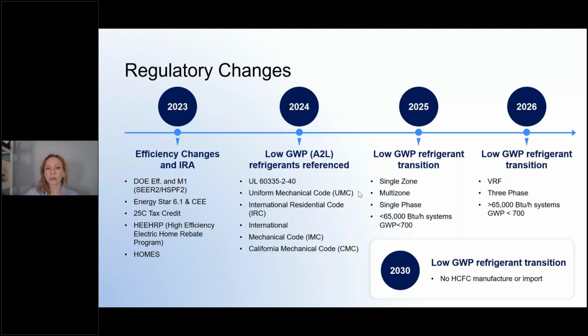As of January 1, 2025, no manufacturers will be allowed to import single phase systems sized 65,000 BTUH or less into the US. There is a sell-through allowance, so equipment already in US distribution or manufacturers' warehouses can be sold through the end of 2025, but as of January 1, 2026, it will no longer be allowed to be installed except for maintenance and repair.